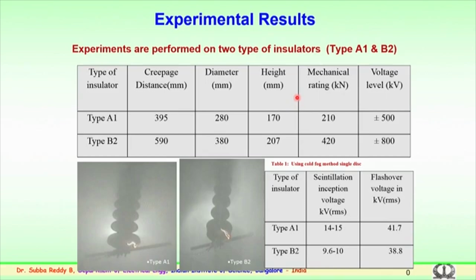For the experiments, insulators of various types from different manufacturers, with different creepage distances and dimensions, have been employed. Several insulators have been tested. A few typical values are shown here. For example, for a particular type A1, the creepage distance is around 395, the disc diameter is 280, the height of the disc is 170, and the mechanical strength of the disc is 210 kilonewton. This is used for plus minus 500 kV voltage levels.